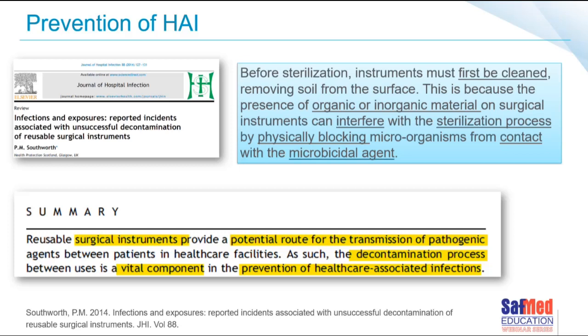Southworth reminds us that before sterilization, instruments must first be cleaned. We need to remove soils from surfaces because the presence of organic or inorganic materials on surgical instruments can interfere with the sterilization process — physically blocking microorganisms from contact with the microbicidal agent, which in steam sterilization would be steam, or in low temperature sterilization could be vaporized peroxide. That bioburden prevents contact with the actual microbial agent, which is why it is so important to clean.